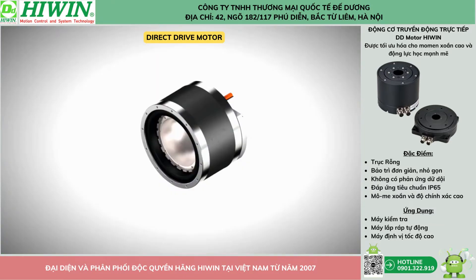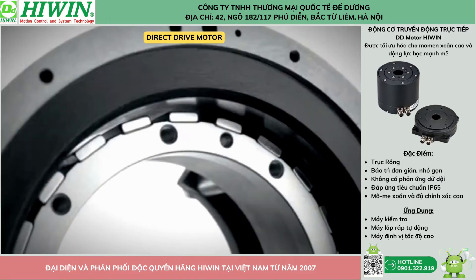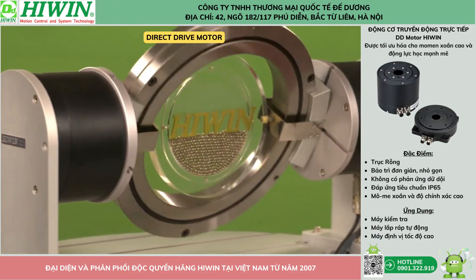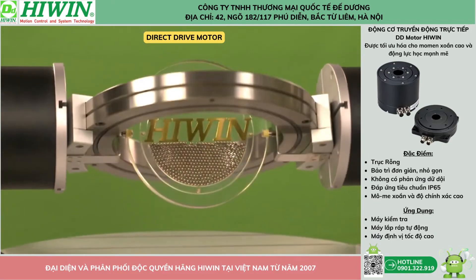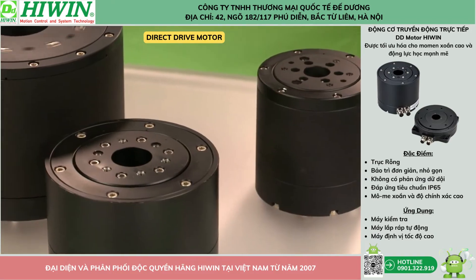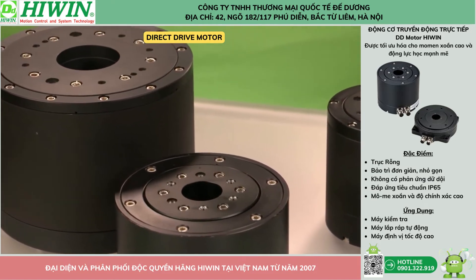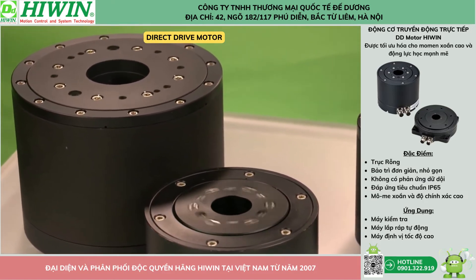Direct drive motors usually have many poles. This lets them output high torque at no or low speed, usually slower than 1,000 RPM. HIWIN's direct drive motors are also highly accurate due to the high-resolution encoder, up to 4.3 million counts per revolution. Repeatability is as low as plus or minus 2.5 arc seconds.